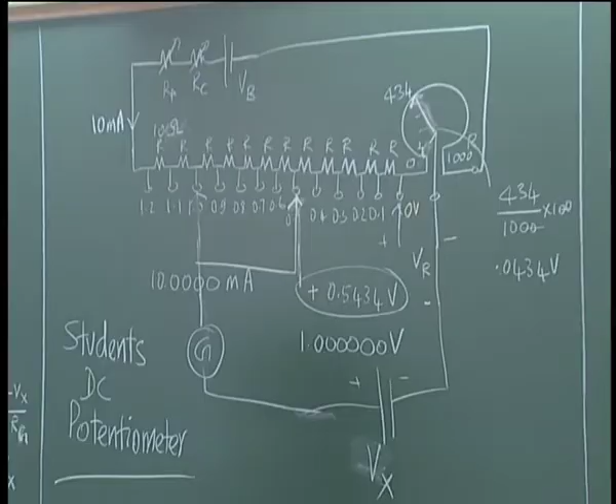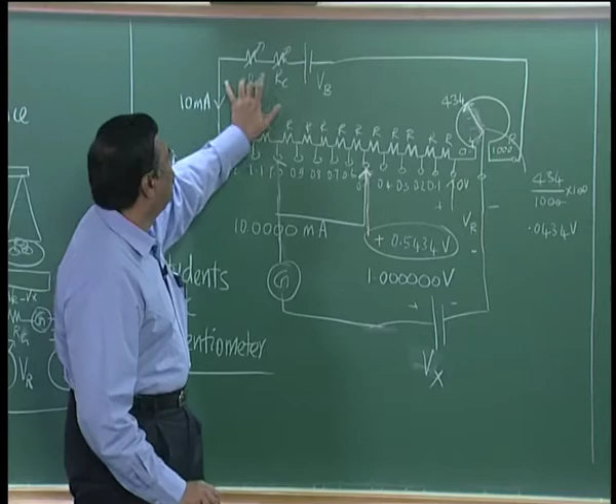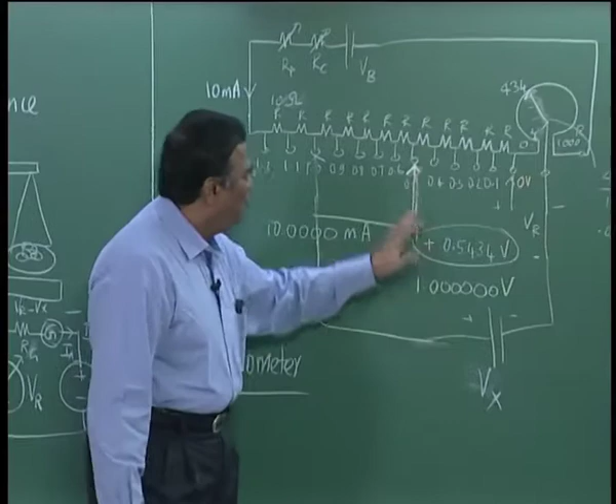Whenever we use a DC potentiometer, we need to do 2 balances, right. The first balance is to make the potentiometer current to be exactly what it has to be, right. That is called standardization. We do it with a standard cell, and we do not adjust the movement on the potentiometer, we adjust the 2 resistors that are in series with the potentiometer circuit to control the current. Once the potentiometer current is set to the exact value that it is required, 10 milliamperes or 1 milliampere, whatever is the design value, then for measurement you move the 2 variable points to get 0, okay.